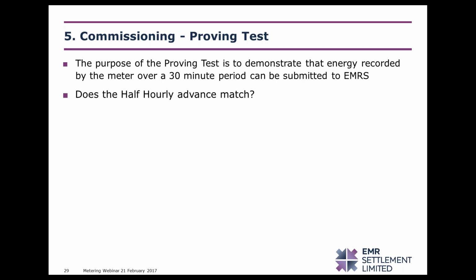The purpose of the proving test is to demonstrate the end-to-end process. So this is that a 30-minute period of energy recorded by the meter can be submitted accurately to EMRS as either through a data collector or directly via the CSV file. This check will confirm that the half-hourly advance at the meter matches what is received by the data collector or the settlement system. There are a number of techniques to do this. You can compare with the cumulative register advance of the meter. You can compare with a download of the half-hourly data of the meter using the meter manufacturer's software. You can compare with an independent half-hourly metering system, or where generation and demand are relatively constant, you can compare with measurements taken at the time of the commissioning. More details on these techniques are available in guidance document G20. I will go through an example using the cumulative register technique.